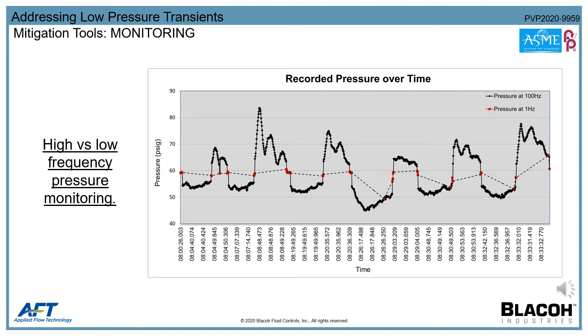The second tool for identifying transient risk is transient pressure monitoring — essentially high-frequency pressure monitoring where pressure is measured multiple times per second. Transient monitors can detect and record pressures 20 to 500 times per second. Normal methods range from dial gauges to SCADA systems recording at one hertz at best. Because transient waves travel near the speed of sound, pressures recorded at only one hertz will convey only bits and pieces of most transient events, missing potentially severe problems that only higher frequency data can reveal.